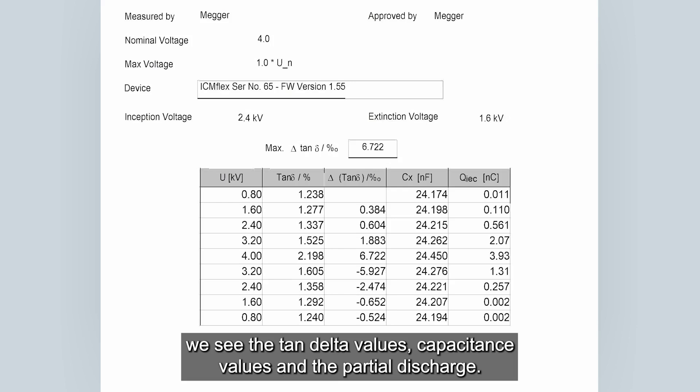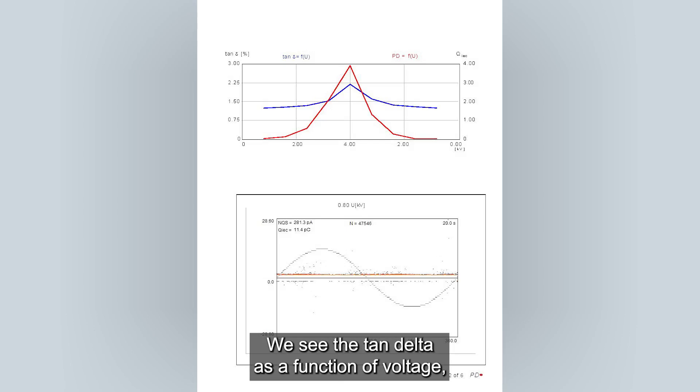We see the tan delta values, capacitance values and the partial discharge. We see the tan delta as a function of voltage and partial discharge value as again function of voltage. And then the first phase result partial discharge pattern at the first voltage level, which was 0.8 kV. That was taken for 20 seconds, which is basically only the background noise.